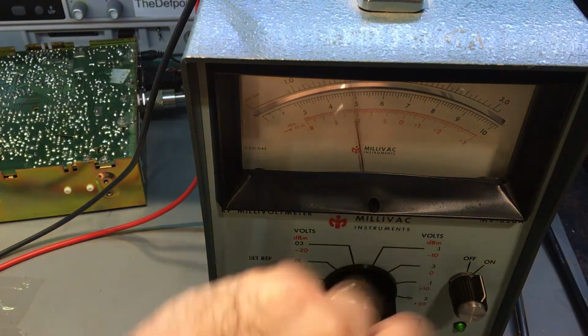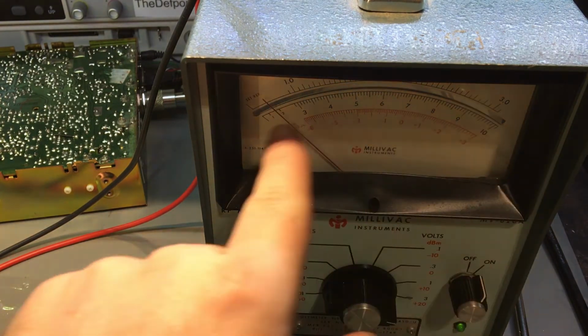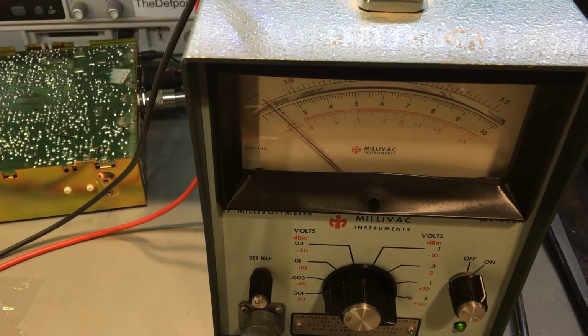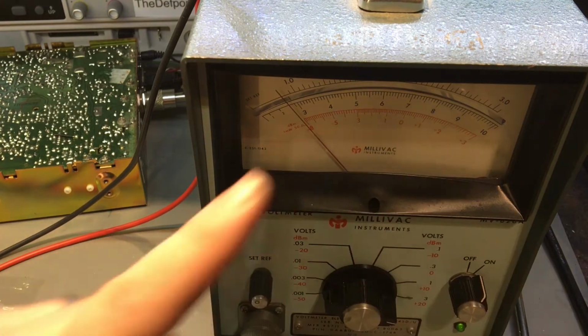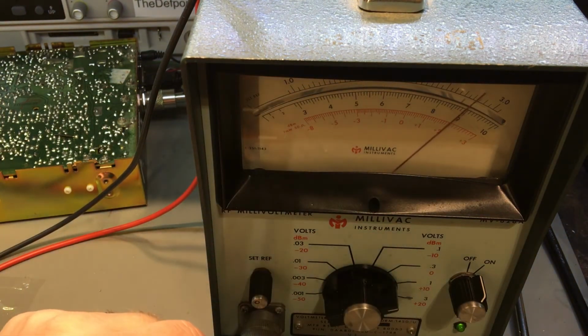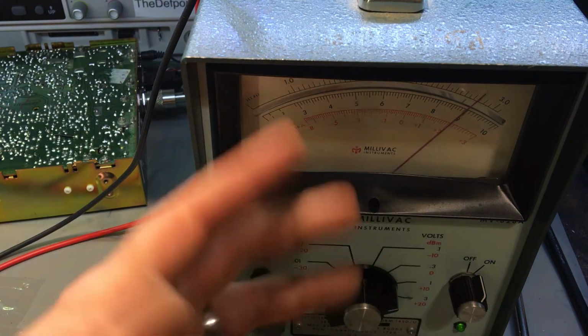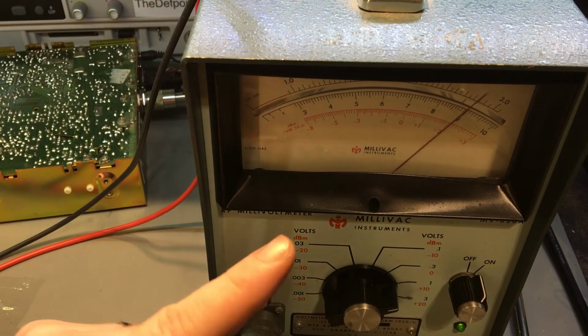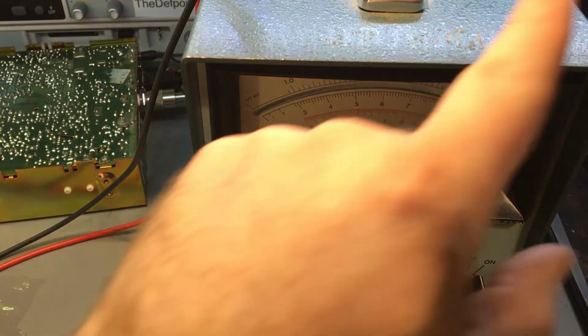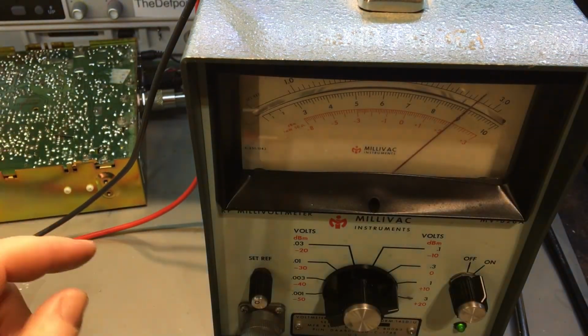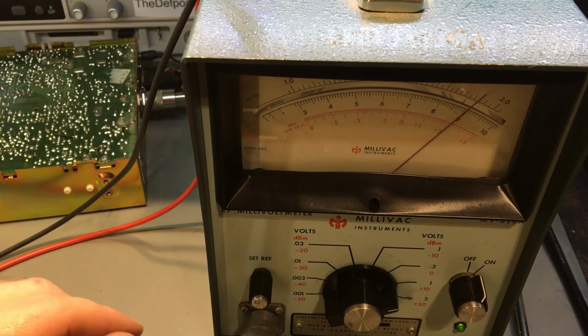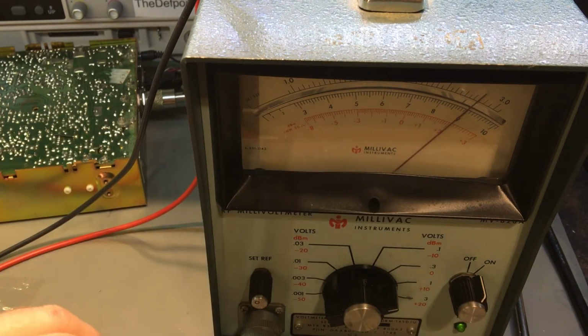And if I go to the 3 volt range, I don't think I'll be able to get it to register in that range because this probably doesn't go high enough output. I don't think it's going to go there. Yeah, 812 millivolts is the highest I can do on my Marconi there, and that looks about right. It's 885 or something on there, so there's a bit of a discrepancy. My Fluke is saying 820 and my Marconi is saying 812, so it could be a slight calibration thing going on there, but otherwise it's not too bad.